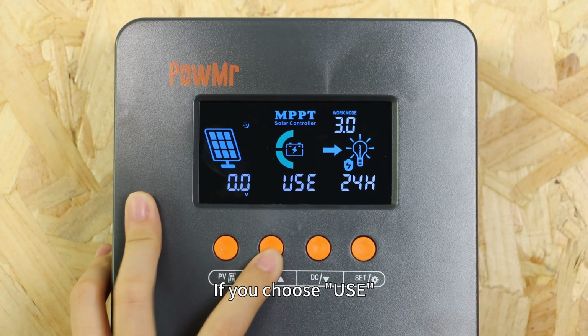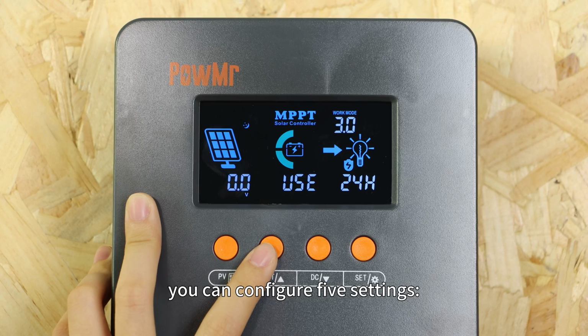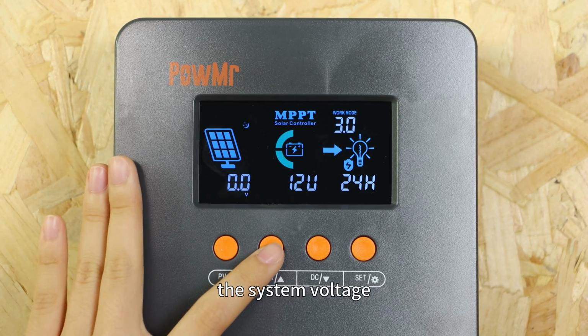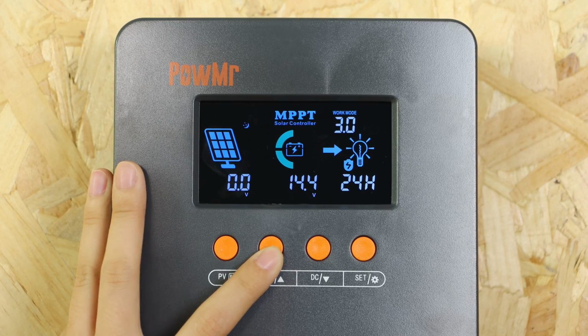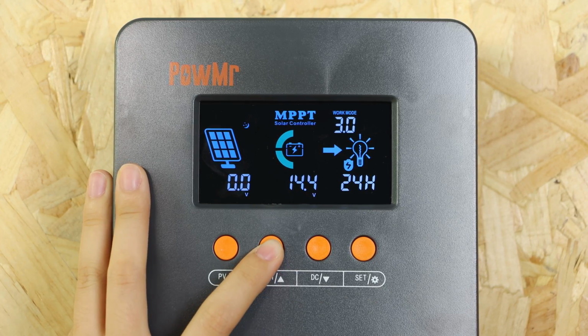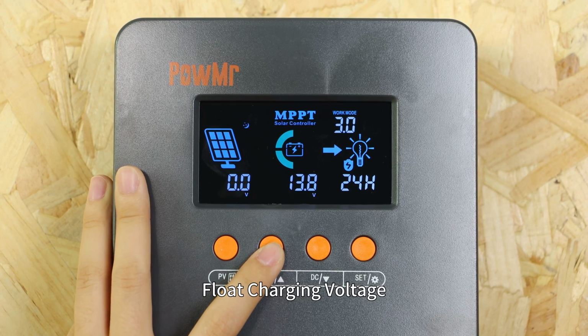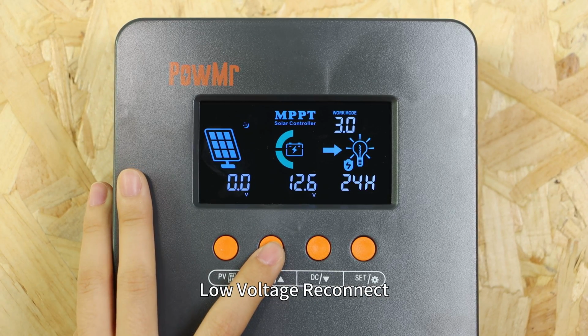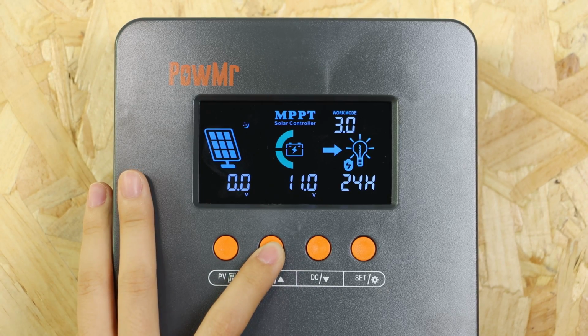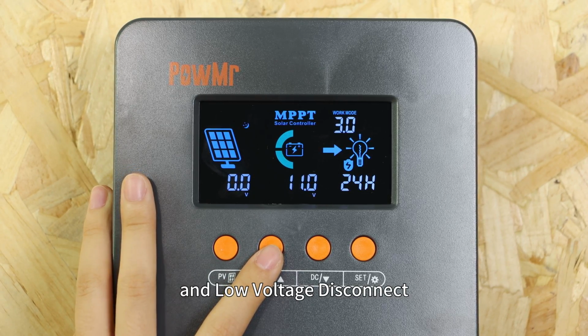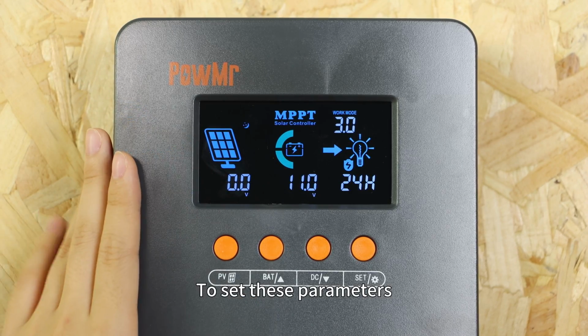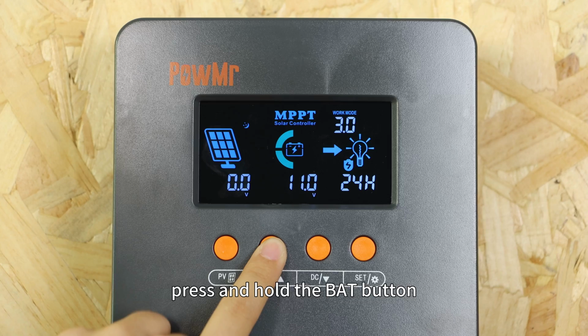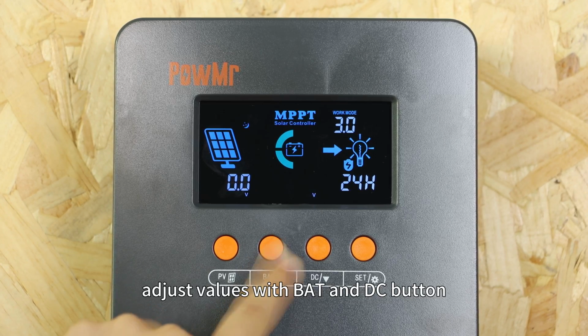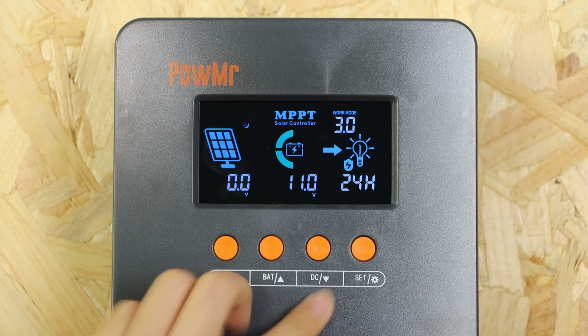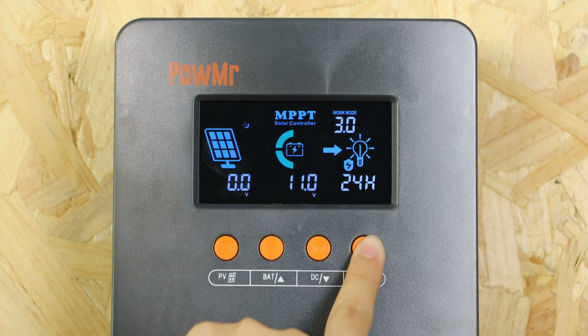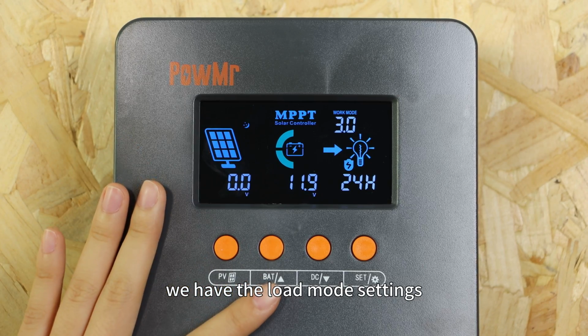If you choose USE, you can configure 5 settings: the system voltage, boost charging voltage, slow charging voltage, low voltage reconnect, and the low voltage disconnect. To set these parameters, press and hold the BAT button, adjust the value with the battery and DC buttons, and confirm with the set button.